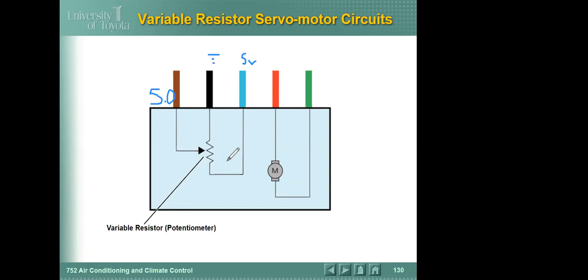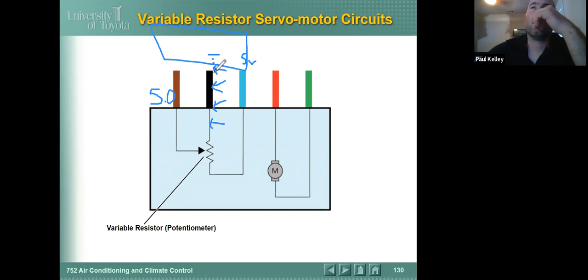So if you get a code and it says short or high voltage, it's probably because you have a problem on the ground. Maybe internally the printed circuit opened, maybe there's a loose connection at the pin, maybe the wire's cut in half, maybe the controller that's the source of the ground has failed. So we don't know if it's the controller up here, the wiring, or the actual component. You need to be able to do voltage tests for that. Picking up what I'm putting down, kind of, sort of.